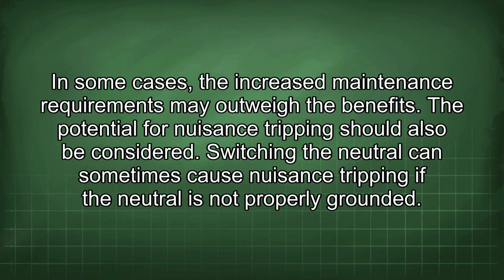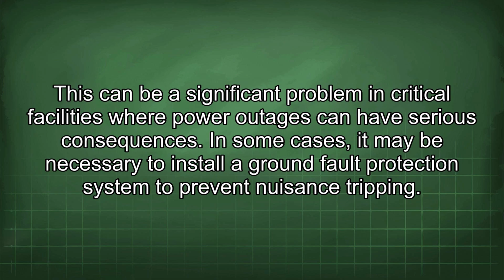The potential for nuisance tripping should also be considered. Switching the neutral can sometimes cause nuisance tripping if the neutral is not properly grounded. This can be a significant problem in critical facilities where power outages can have serious consequences. In some cases, it may be necessary to install a ground fault protection system to prevent nuisance tripping.